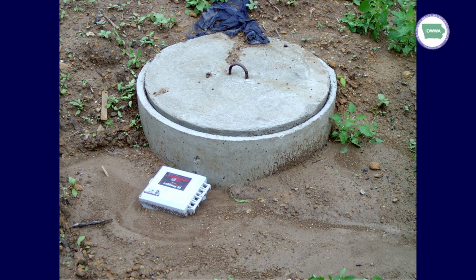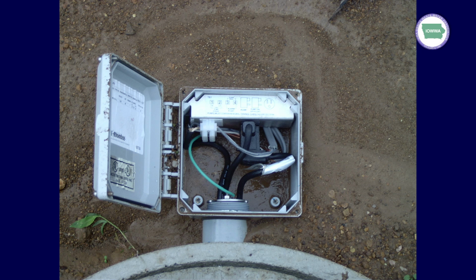Here's an example of an installation with one of our products. They did everything right. This JB plugger is designed to go into the ground beside your riser, and you're going to use a conduit seal there. That seals off gas. What they didn't do is secure the lid down tight and screw it in so the NEMA rated gasket can seal everything off. I don't know if you can tell, but that's mud in there.